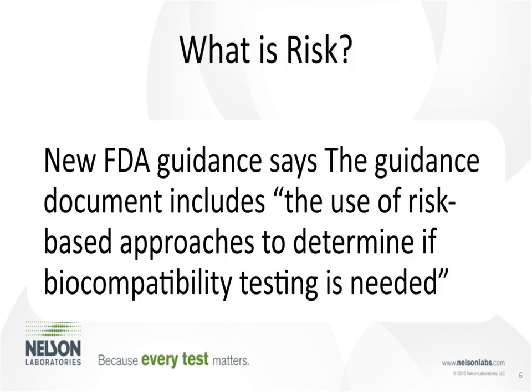The FDA guidance says the document includes the use of a risk-based approach to determine if biocompatibility testing is needed. That's a quote from the guidance document. It says if biocompatibility testing is needed. And that's the main thing that I hope you get out of this presentation: biocompatibility should not be a checkbox mentality anymore.